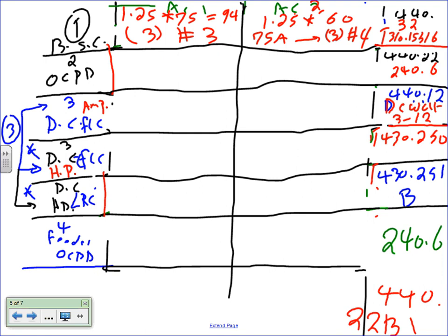Okay? And I know I've done it differently another time, 1.75, but if you read it, guys, it tells you if it doesn't start, go to 2.25. Let's assume the worst scenario, 2.25, multiplied by the same 75, and if you go there, it will give you 169, and that will translate into a healthy down to 150 amp. And you go down, don't forget the down.